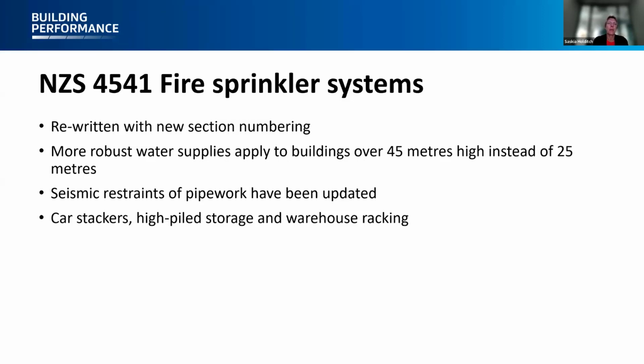Buildings over 45 meters high now have to comply with more robust water supplies instead of at 25 meters. So for buildings between 25 and 45 meters high, the requirements have become a bit less stringent - it's more cost effective, with no increase in risk that the sprinkler will fail. The seismic restraints for the pipework have been updated, and there have been changes with car stackers, high piled storage, and warehouse racking, based on research done in the States to make sure we're aligned with the latest findings.